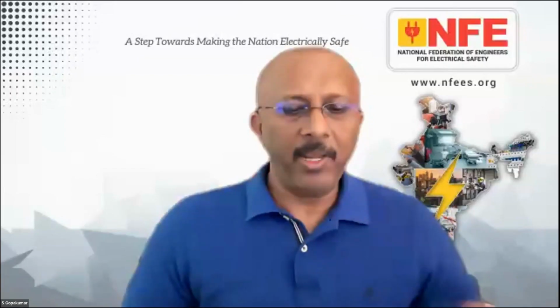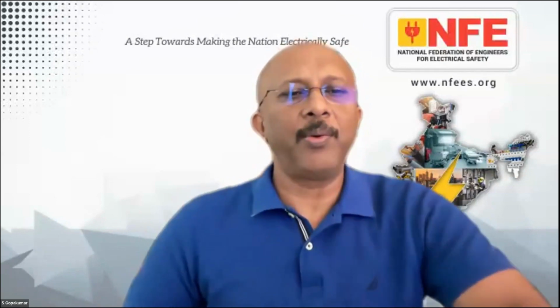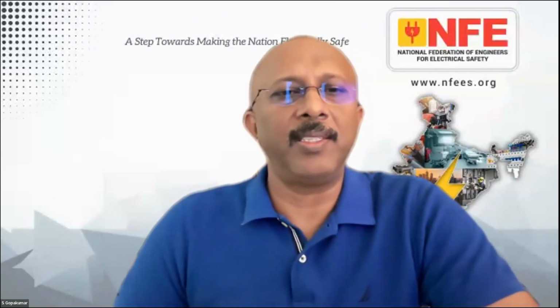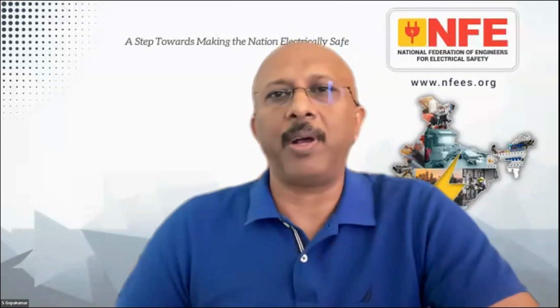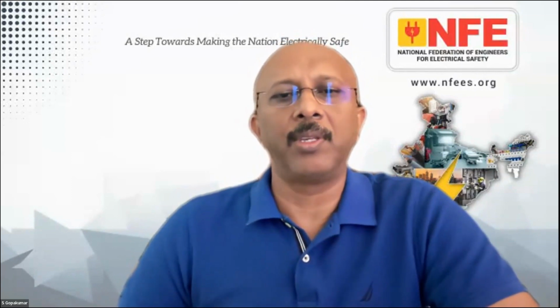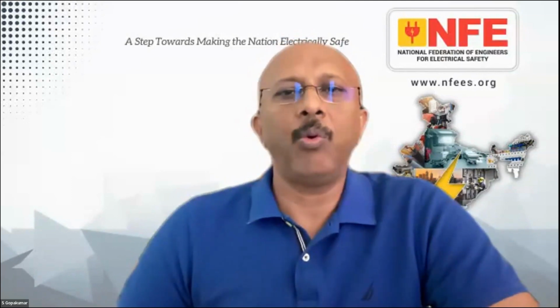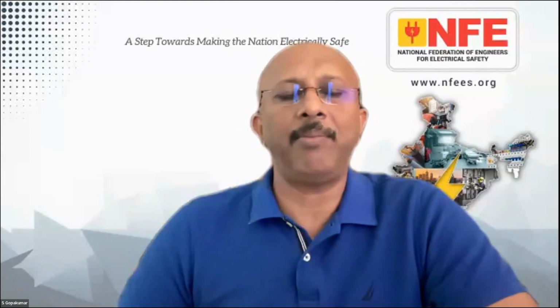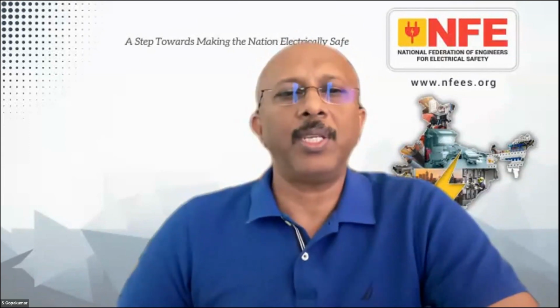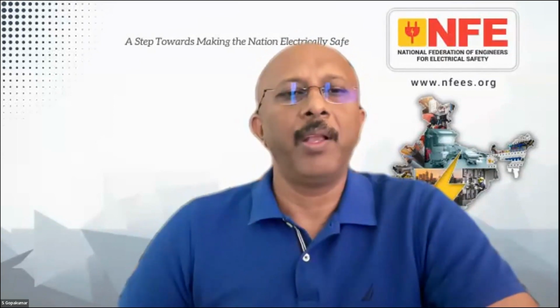Yeah, thank you. Actually, in the Indian context, I would like to elaborate on this answer a little more, because I have found in a lot of cases the protective devices are overrated. Three days back, I was checking a case where the protective device was a C-type MCB rated for 63 amps, and the outgoing circuit wires from the protective device were 2.5 square millimeter wires.